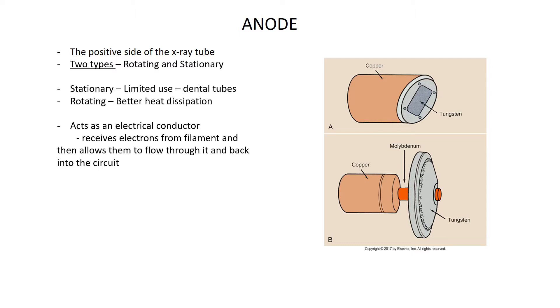The anode acts as an electrical conductor. It receives the electrons from the filament and then allows them to flow through it and back into the circuit. Remember, a circuit has to be a closed path. You have the filament, then a gap, then the anode. When you push the exposure button, the electrons are boiled off the filament, travel across the gap, and strike the anode — where heat and x-rays are made. Then the electrons travel back into the circuit.